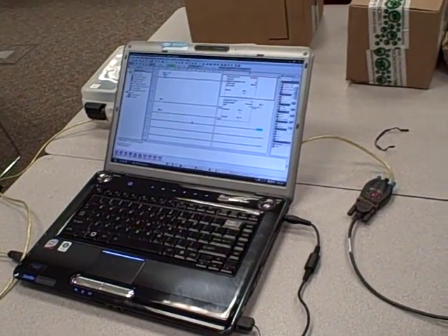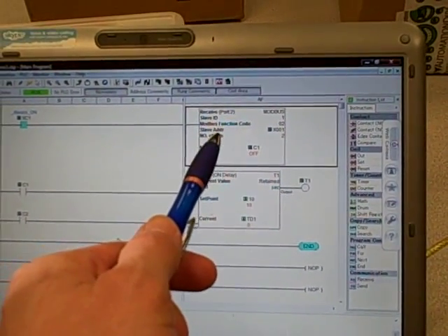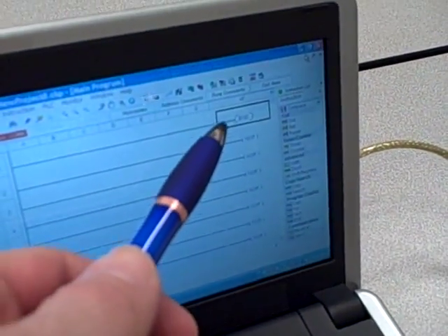In this video, we're demonstrating the use of Modbus to exchange data between two PLCs, a master PLC and a slave PLC. In this particular exercise, what we're going to be doing in the master PLC is using a Modbus receive command. We're going to be pulling or grabbing data from the slave PLC and bringing it in the form of bits. In the slave PLC, which is slave address number 1, we have no program whatsoever. We simply have an end statement.